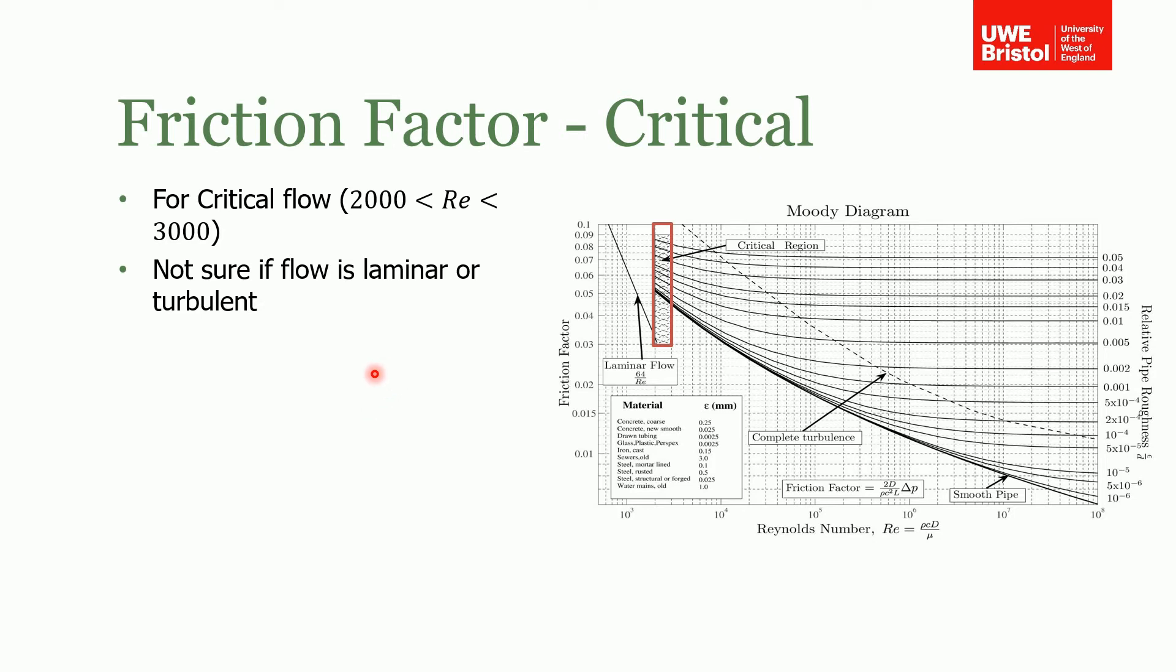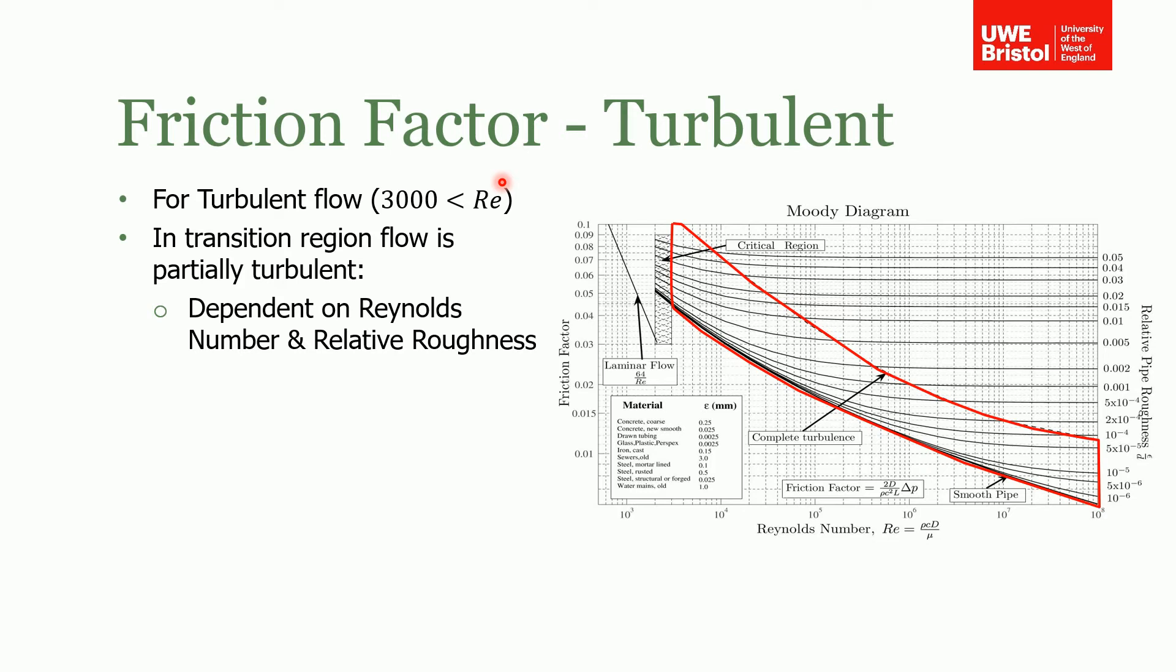The turbulent region can be broken up into two sub-regions. One is the partially turbulent region and the other is fully turbulent. On the plot here you can see that I've got the partially turbulent region highlighted, and in this area if you look at the gradient of the lines of relative pipe roughness, or more importantly friction factor, you can see that the friction factor is dependent on both the Reynolds number and the relative pipe roughness. So you look up your roughness, but this is changing; the friction factor is changing with Reynolds number.